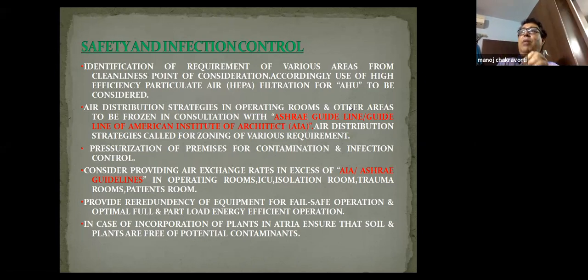So my chiller power consumption also will be coming down, plus my pumping cost also will be coming down, because I don't need to pump that much chilled water into the coil, because my load has come down. So my chiller consumption has come down, my pump consumption has come down, and my AHU fan consumption has come down. So I am saving that much energy.